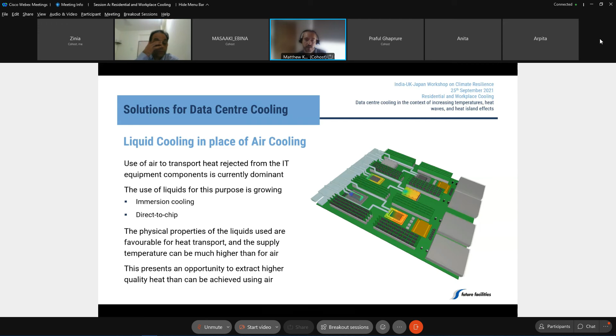The move to liquid cooling has seen increasing engagement between IT equipment manufacturers and data center operators. Fundamentally, data center design and operation reflects the needs of the IT equipment manufacturers produce, and changes to computing hardware design could help accommodate increasing ambient temperatures. For example, increased temperature tolerance of IT could prevent increasing failure rates at higher supply temperatures. Reduced power demand through improved computing performance per watt could help reduce the power draw and overall cooling requirement for an IT workload. Finally, avoiding unnecessary increases in power density and reductions in size could help.